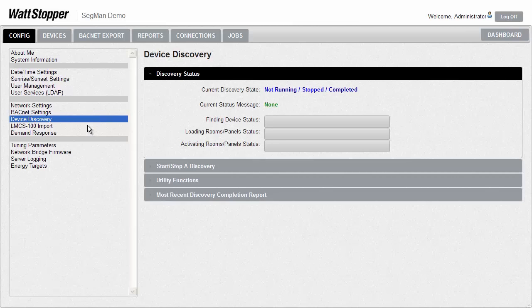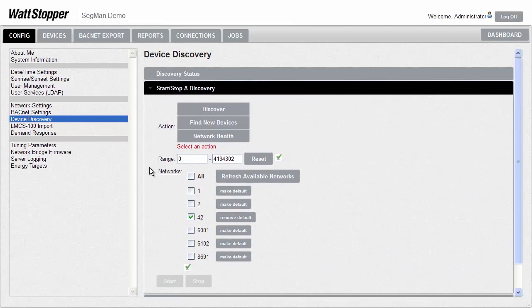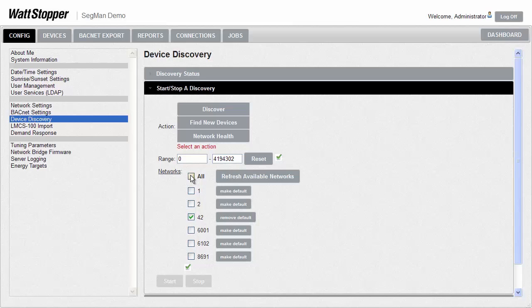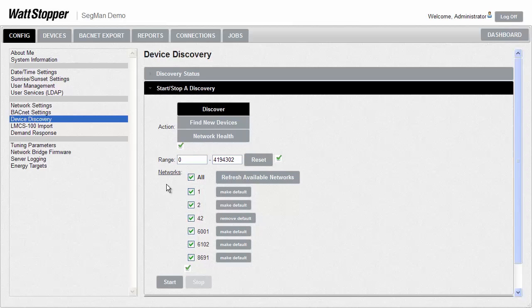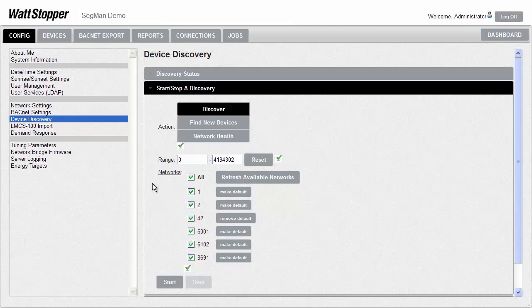Someone setting up a Segment Manager for the first time, typically one of our technicians, would use the Device Discovery option. They would start by going to the Start/Stop A Discovery slider, and then select all the networks connected to the Segment Manager that they'd want to check for our LMBC 300 network bridges. They would then select the Discover button, and finally they would click on the Start button. Once the discovery has started, the Segment Manager will reach out across the specified MSTP segment networks and start communicating with all the network bridges in each individual room and any LMCP relay panel. The bridges will provide the Segment Manager with information detailing every individual DLM device in that space, as well as key settings in those devices.